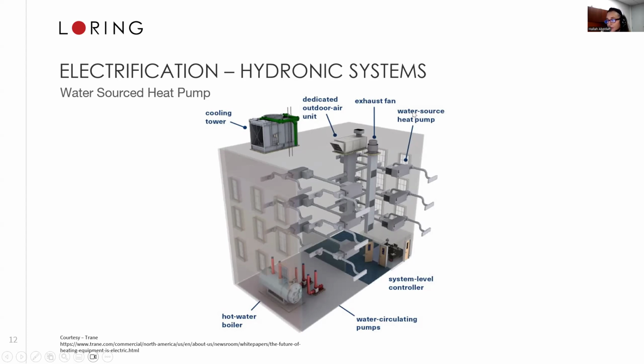And this system works really well for large applications. The caveat here is that in very cold weather climates, the outdoor conditions might become so cold that a heat pump solution is not able to really create that differential or temperature gradient with the outside conditions. And that's where we come in and add another source of hot water to be pumped into the building, or supplement or boost the cycle. And this is often done through a hot water boiler, which, again, we're trying to walk away from in a decarbonization strategy.